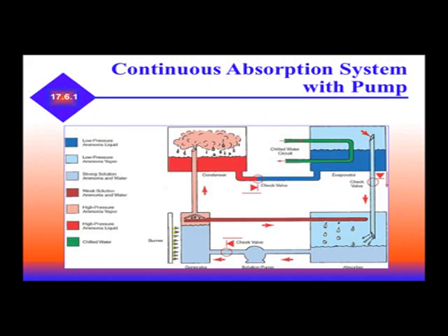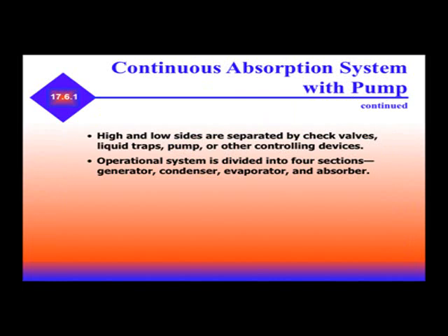This is a continuous absorption system with a pump. You'll notice the condenser, a check valve and pump, and we circulate chilled water through the evaporator — so this is a chiller system. High and low sides are separated by check valves, liquid traps, a pump, or other controlling devices. The operational system is divided into four sections: generator, condenser, evaporator, and absorber.